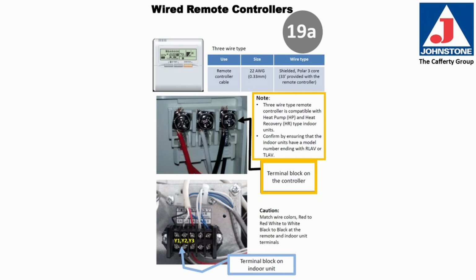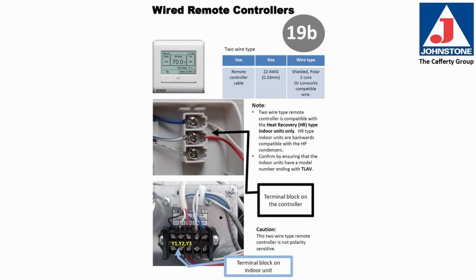Here's the terminal block on the remote controller. Match the wire colors, red to red, white to white, black to black, at the remote controller and the terminal block on the indoor unit. Here's the wire layout for the 2-wire type controllers. This is remote control cable, 22 gauge, shielded, polar, 2-core, LonWorks compatible wire.